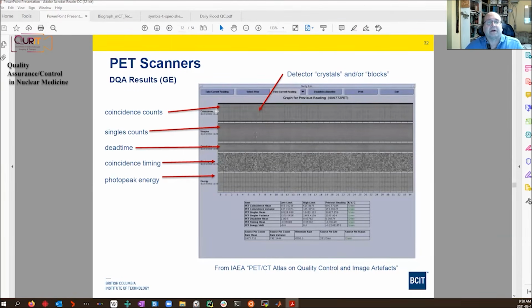And these are images based on the coincidence count rate, the singles count rate, the dead time. I'm not going to go into the details of that. Coincidence timing, energy. If there's anything that is particularly non-uniform, or more commonly, if this changes from one day to the next, it'll alert you that something has gone wrong, either in the components or the calibration.